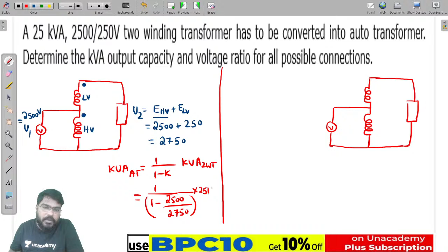Therefore we can write kVA rating of auto transformer equals 1/(1-k) times the kVA rating of the two winding transformer. Got my point? So now let us find 1/(1-k), which is low voltage by high voltage. So 2500 divided by 2750, into 25 kVA.